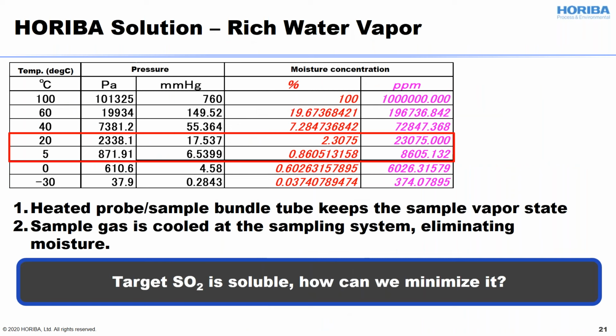Okay, let's take a look at how we can resolve the problem of rich water vapor and corrosive gas. First of all, I'm taking a look at how we treat this rich water vapor. The table here simply shows a higher temperature can hold more water in the gas. This is why you want to keep that gas hot to keep the vapor state, and then cool the gas in the sampling system to knock the moisture out. By doing this, we can drop the moisture and the sample gas can be dry.